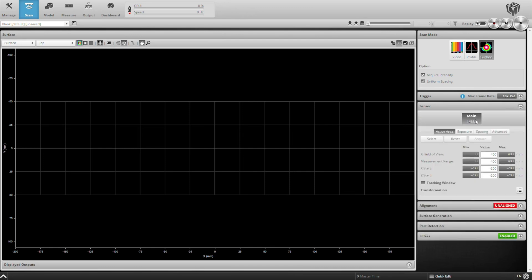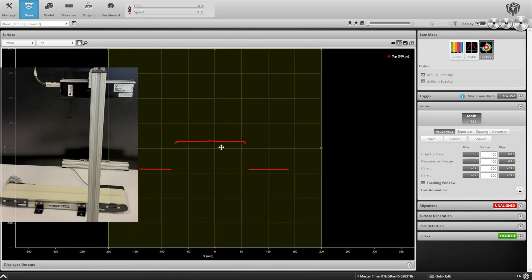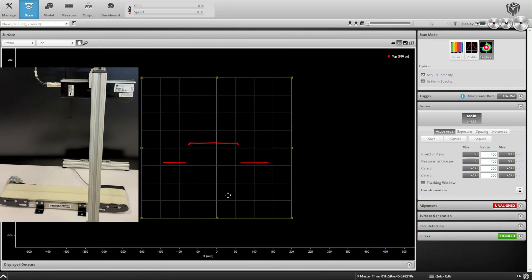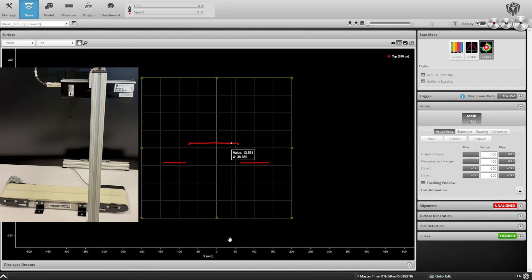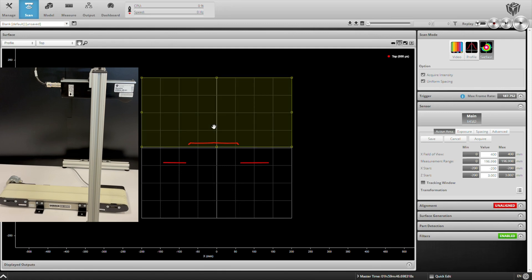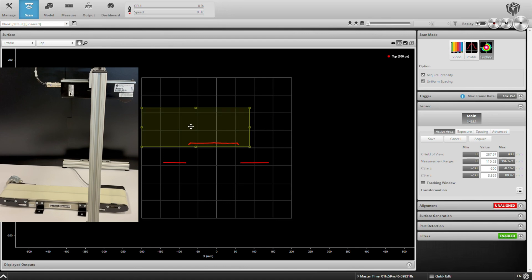So the 3D system won't need another device or sensor or PLC to tell it when individual parts come by. We'll automatically scan them and singulate them and then inspect or measure them. First thing we're going to do is adjust our active area, which is the sensor's field of view. This particular model is capable of seeing a large area. We're going to narrow that field down so that we don't see the table, for example, and also so that we increase our frame rate.